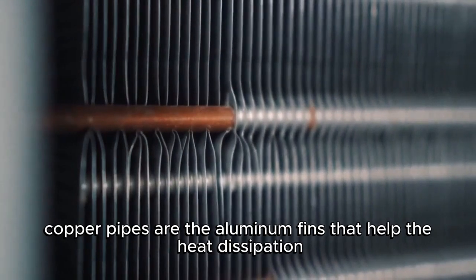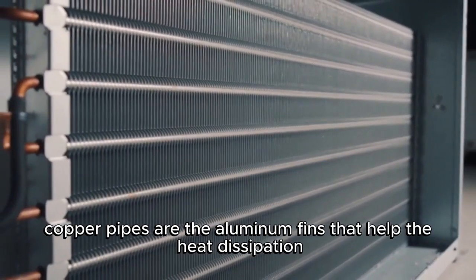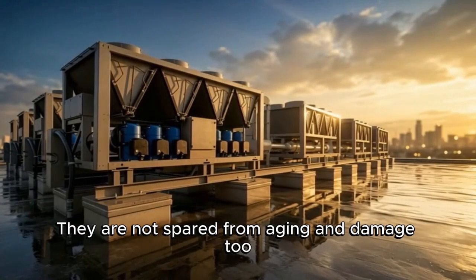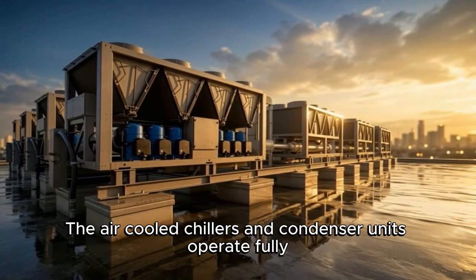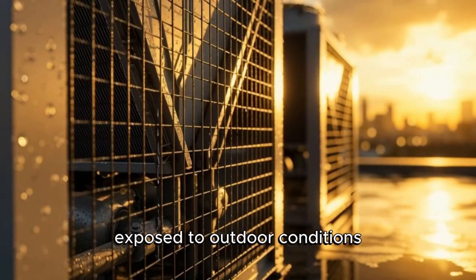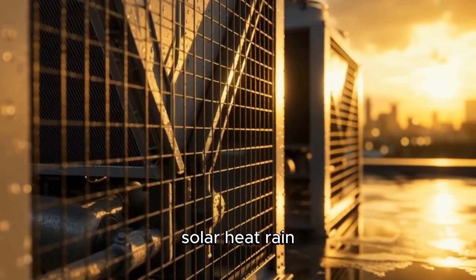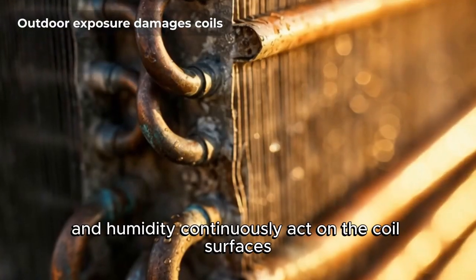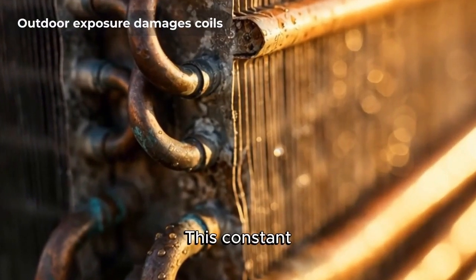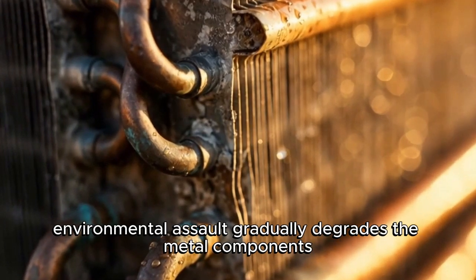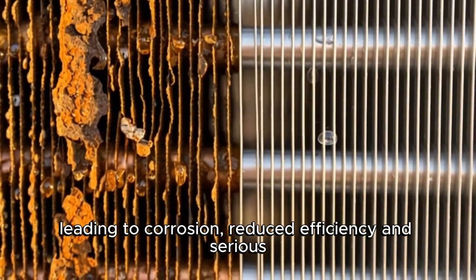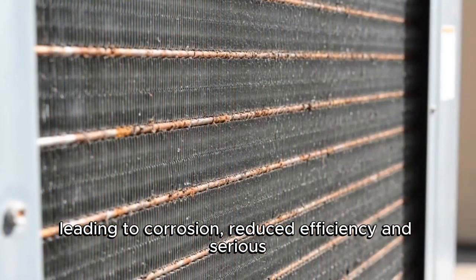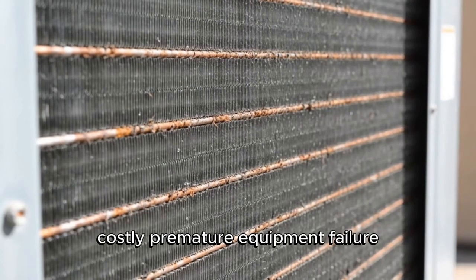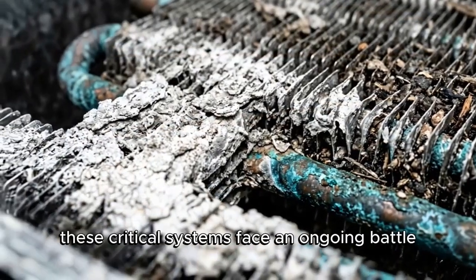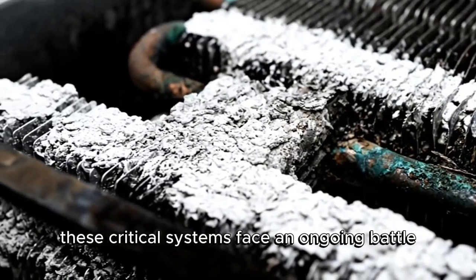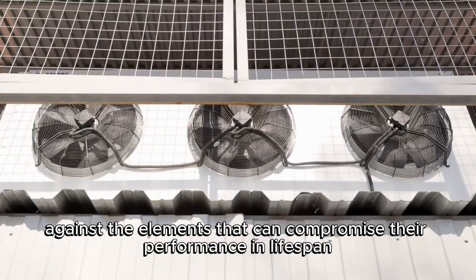Outside the refrigerant copper pipes are the aluminum fins that help the heat dissipation. They are not spared from aging and damage too. The air-cooled chillers and condenser units operate fully exposed to outdoor conditions. Solar heat, rain, and humidity continuously act on the coil surfaces. This constant environmental assault gradually degrades the metal components, leading to corrosion, reduced efficiency, and serious, costly premature equipment failure. Without proper protection, these critical systems face an ongoing battle against the elements that can compromise their performance and lifespan.